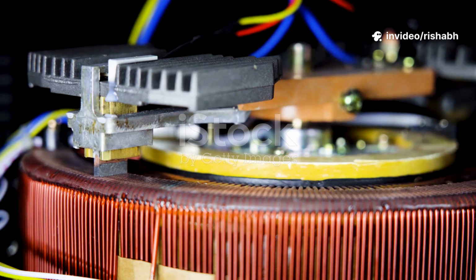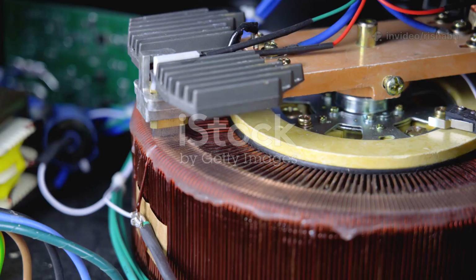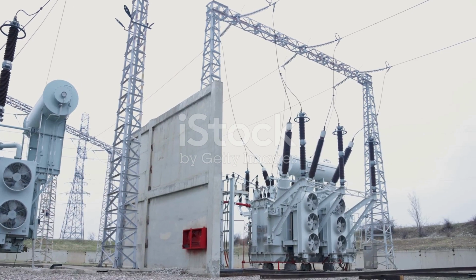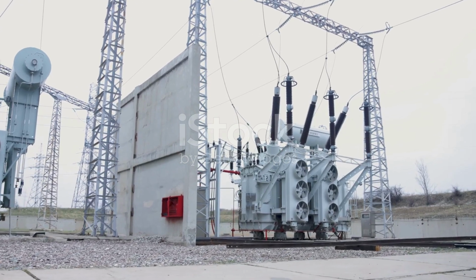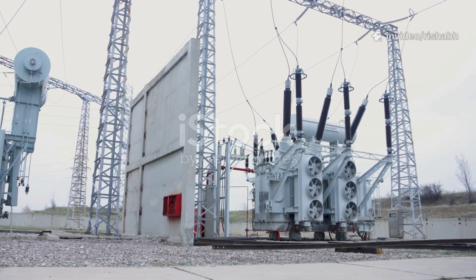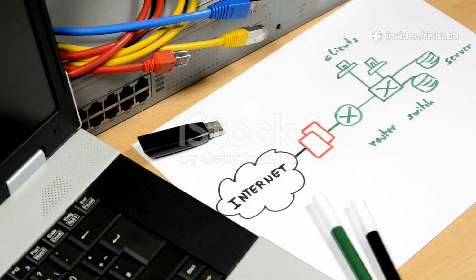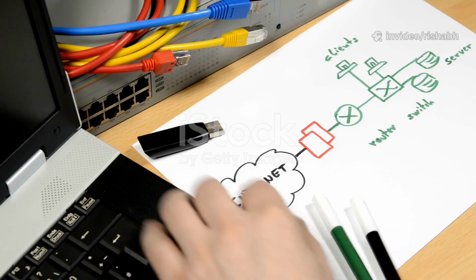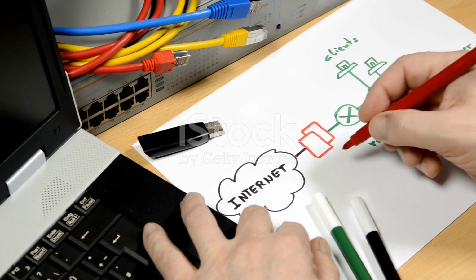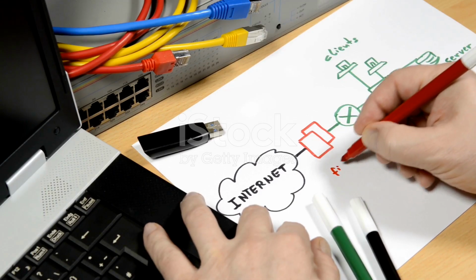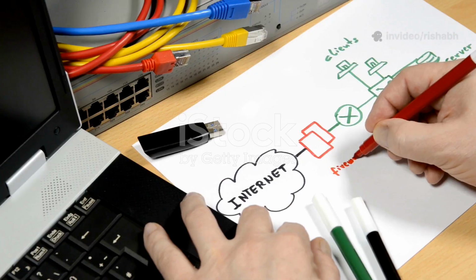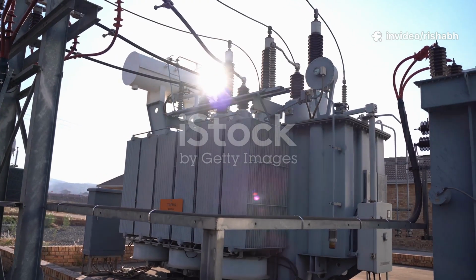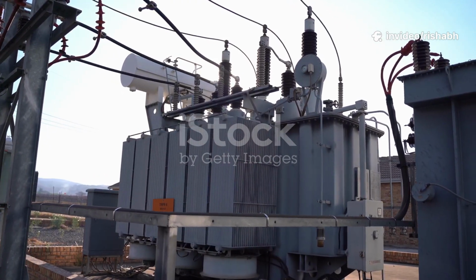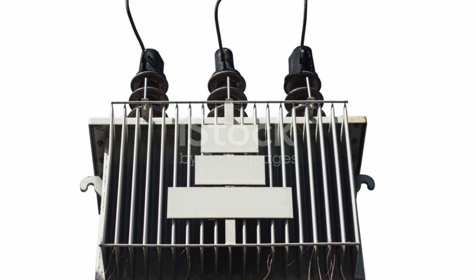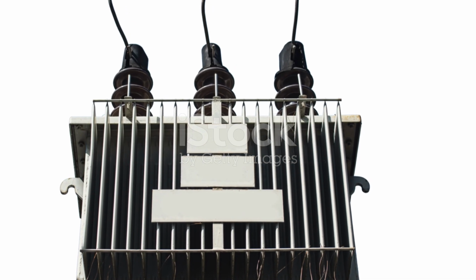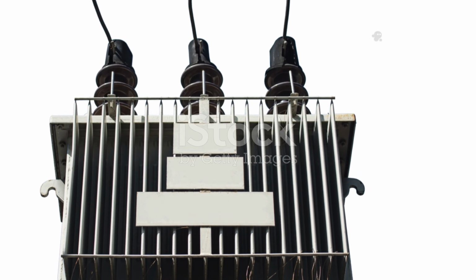So, what exactly is a vector group? Let's start with the basics. A three-phase transformer has two sets of windings, a primary, high-voltage winding, and a secondary, low-voltage winding. Each of these sets can be connected in one of two main ways: delta, symbolized by a D or d, or star, also called Y, symbolized by a Y or y. A delta connection looks like a triangle, connecting the windings end to end. A star connection brings one end of each of the three windings to a common point, called the neutral, which can then be connected to the ground.